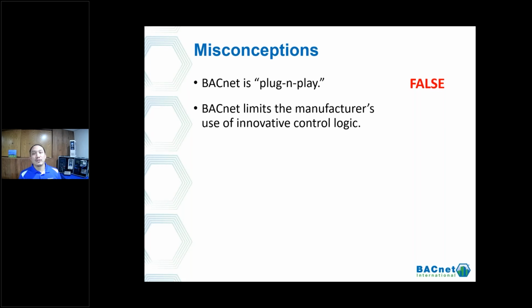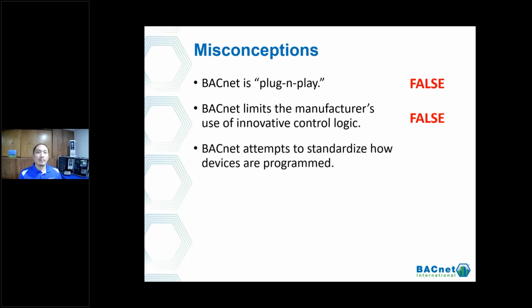Another misconception: BACnet limits the manufacturer's use of innovative control logic, and that couldn't be more false. Every manufacturer, whether it be VFD, lighting, or anyone else, still has control of how their devices work and what type of innovations they put in there. There's a reason BACnet gives us the ability to create vendor objects, so that we can explore new ways and new things to do with that and be more innovative and keep things moving forward. BACnet is just a way to help us define the information that's in there and help people implement and integrate.